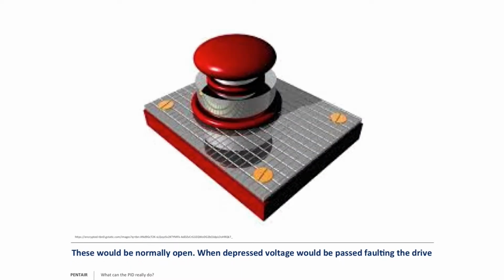Another good example is a safety switch or a dead stop maybe. This button would normally be open, so there's no voltage passing. But let's say we're trying to fill a tank as a reservoir, and we see that it's starting to overflow and we want to stop it suddenly. You push the button, now the button snaps closed. Voltage is now applied to input 1, input 2, however you programmed it. It sees the voltage, and we programmed that to then fault, and it will tell you external fault, telling you that it sees voltage applied to that input.